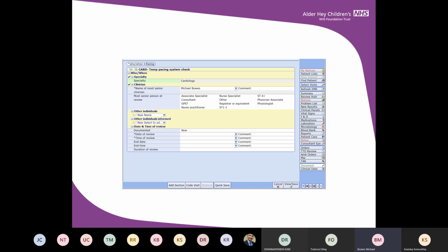And so we've launched this Meditech form to ensure that on a regular basis we're confirming that we're happy with the temporary pacing systems in place, and hopefully to document any changes, so that it's less tempting for people to wander up to the bedside and make some changes and walk away again without anyone being any the wiser. It will also avert issues such as we've had recently, where the A wire was plugged into the V port and the V wire plugged into the A port, and there were difficulties gaining the pacing solutions that we needed, and we don't know how long it had been in that configuration because it wasn't documented. So hopefully this will avoid it.